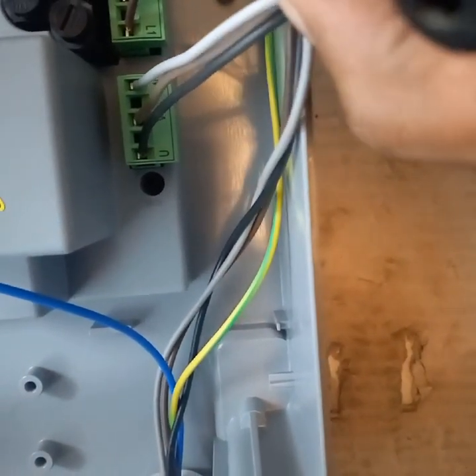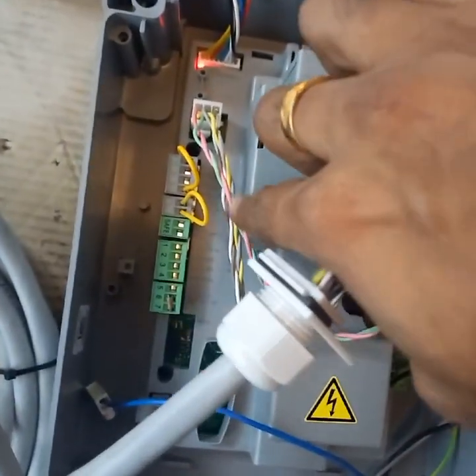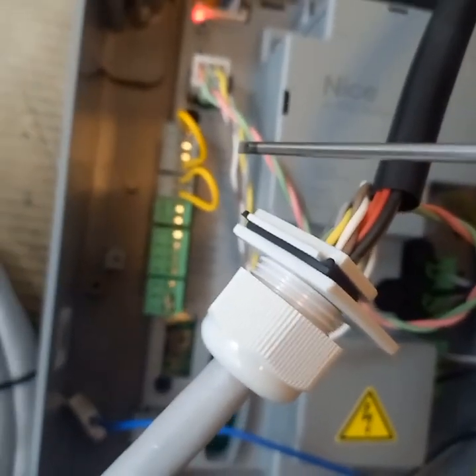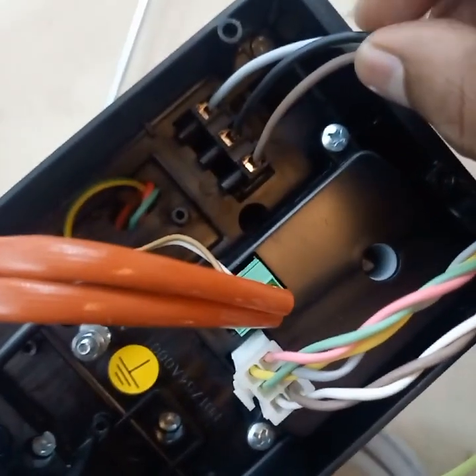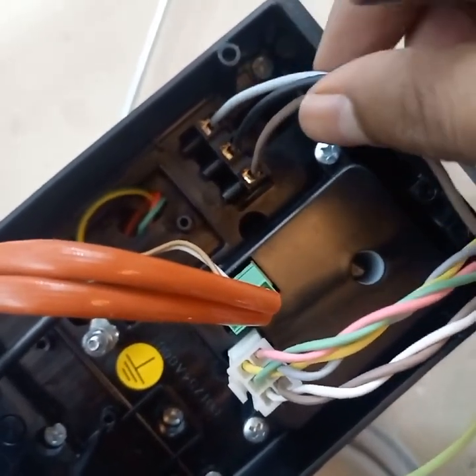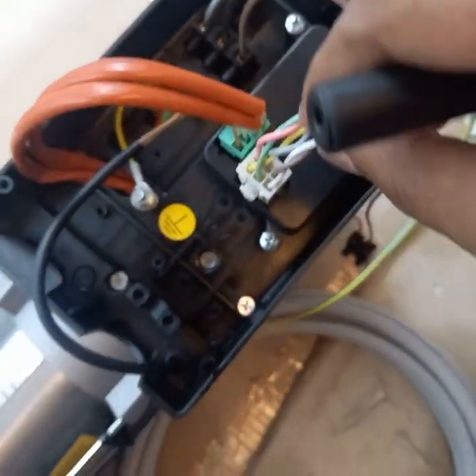W is gray. You need to connect the encoder here and put the jumpers for photocell and save. In the motor there is a connector coming — brown, black and gray — in this same position, and the encoder connection should be terminated here.